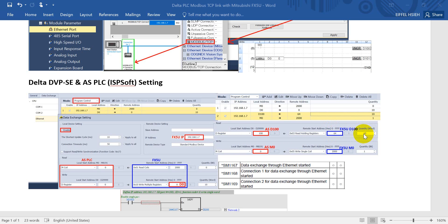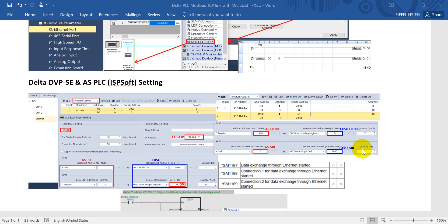We define AS PLC D100 will get the status from FX5U D100, so the Modbus address is 64 and we get 10 devices. Then we will write the M0 from AS PLC to FX5U M0, so here we'll use the 2000. You can see this is the data exchange table or content and we assign write only one.